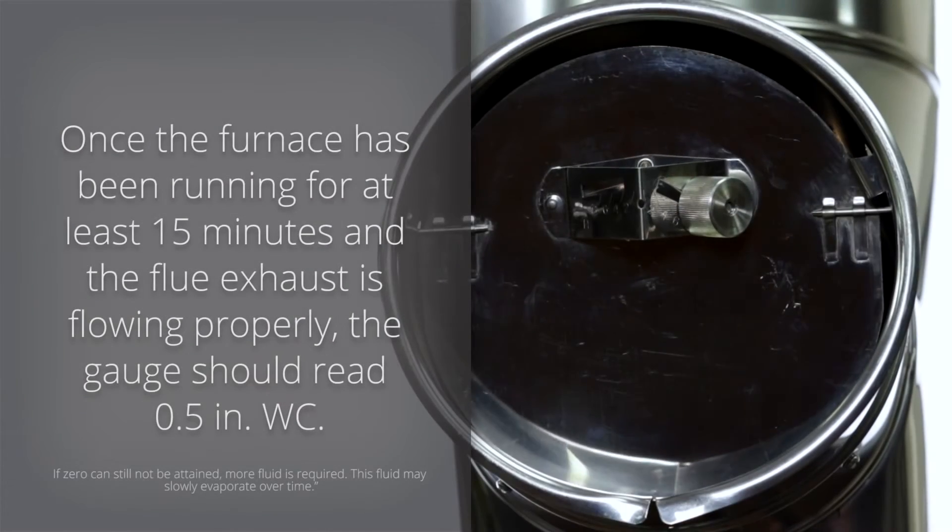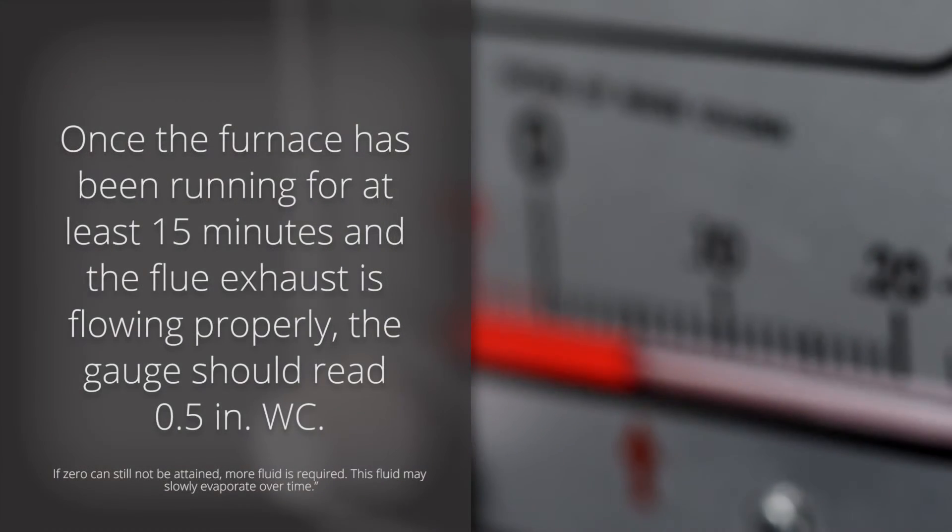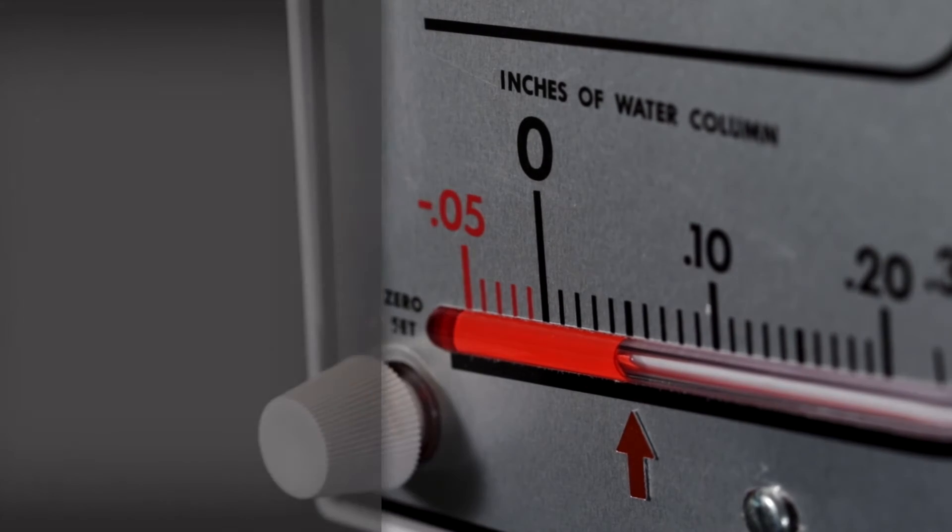Once the furnace has been running for at least 15 minutes and the flue exhaust is flowing properly, the gauge should read 0.05 inches of water column.